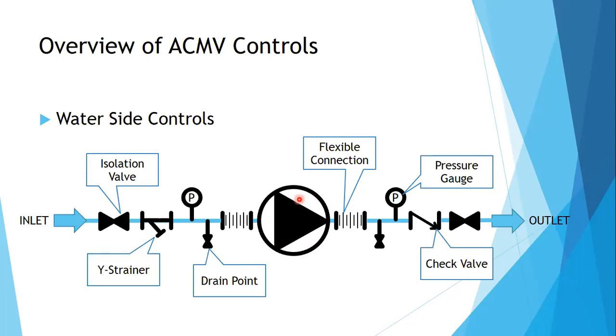Based on the pump and based on your electrical power consumption, you will be able to gauge or have an estimate. You can plot it on your pump curve. What is the performance of your pump? Again, drain points. Don't forget your drain points. During operation, drain points are kind of useless. But during installation, drain points are very, very important and very, very useful.